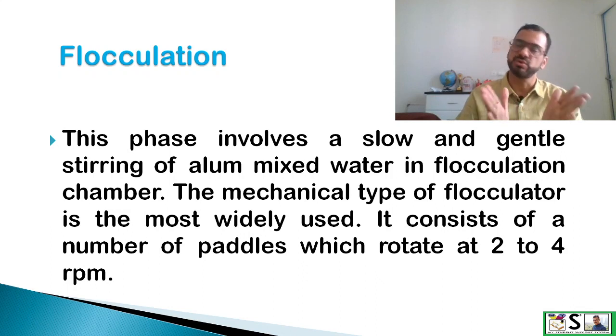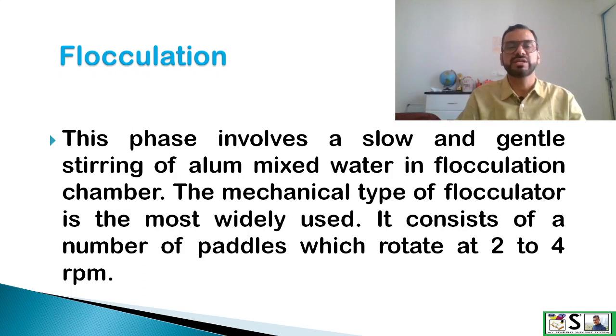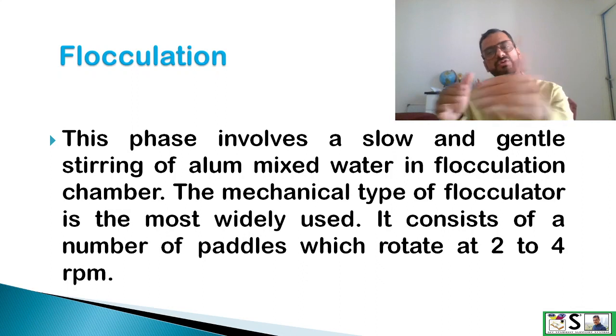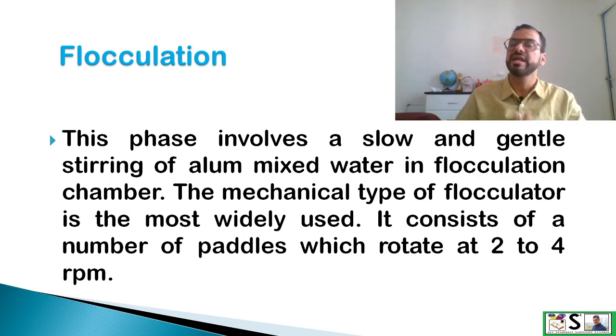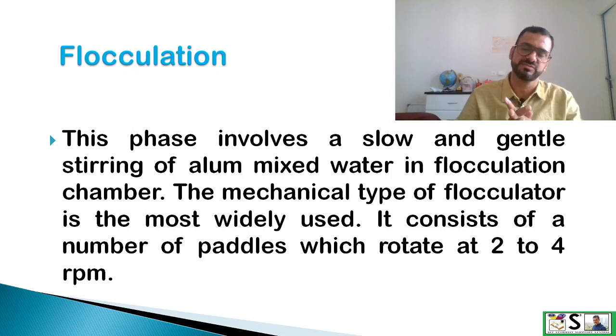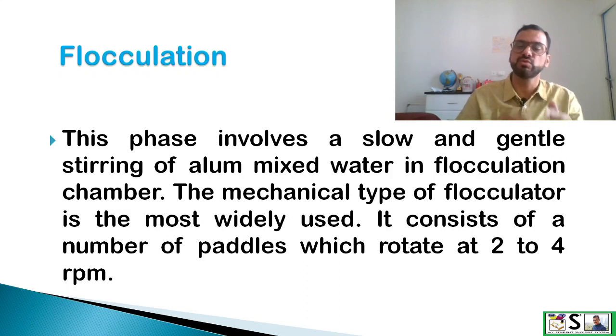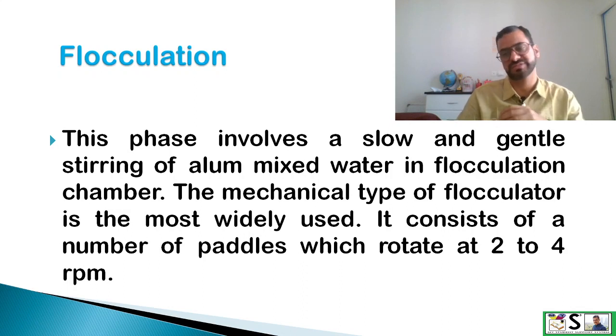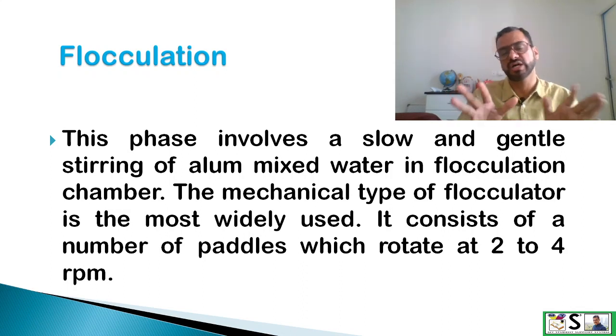The next phase is flocculation. The water mixed with alum is sent to the flocculation chamber where slow mechanical stirring causes proper flocculation or coagulation in the water. The mechanical type of flocculators is most widely used in water treatment plants and consists of a number of paddles which rotate at 2 to 4 rpm.